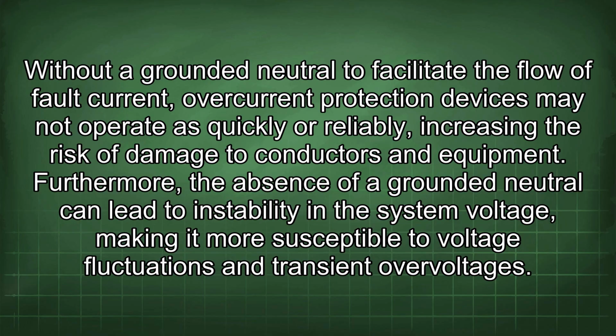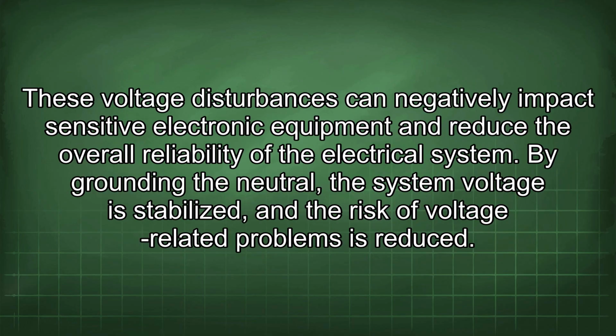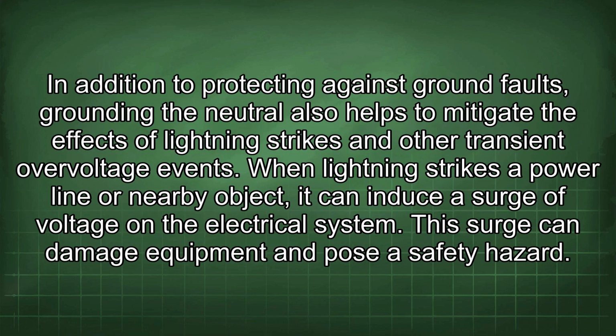Furthermore, the absence of a grounded neutral can lead to instability in the system voltage, making it more susceptible to voltage fluctuations and transient overvoltages. These voltage disturbances can negatively impact sensitive electronic equipment and reduce the overall reliability of the electrical system. By grounding the neutral, the system voltage is stabilized, and the risk of voltage-related problems is reduced. In addition to protecting against ground faults, grounding the neutral also helps to mitigate the effects of lightning strikes and other transient overvoltage events. When lightning strikes a power line or nearby object, it can induce a surge of voltage on the electrical system. This surge can damage equipment and pose a safety hazard.